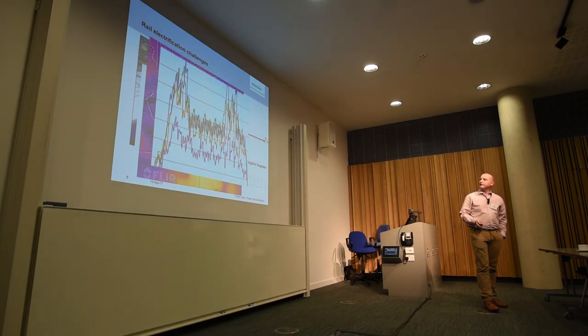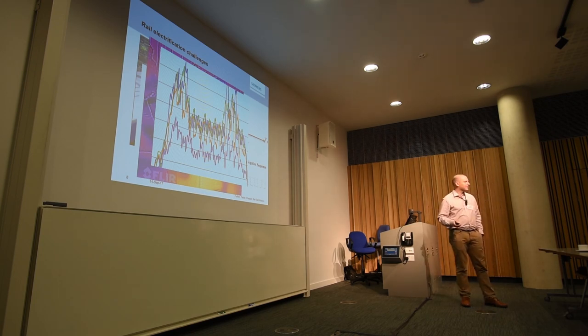And the load is very peaky. You're looking at four different supply points there, and both loads do not line up, so the negative phase sequence doesn't balance out at the adjacent sites. Also, your thermal rating, getting more out of the existing system, is all about RMS, so it's typically a 30-minute time constant. The RMS load is much higher than the average. Now you're starting to see where energy storage possibly fits in - what can you do to avoid those wires through that tunnel, and what can you do to take out some of those peaks and just smooth that curve?